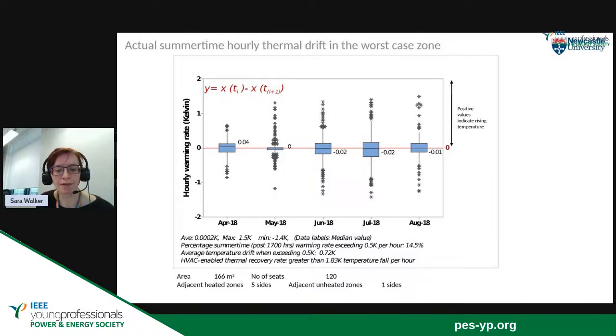Cooling was happening relatively slowly, but for some periods of the year, during the cooling period, warming up was happening faster than comfortable for over 14% of the cooling period that we looked at. So we can offer demand response in summer, but potentially for some spaces, or when external temperatures are particularly high, we might not be able to offer demand response because of this slightly faster warming up of the building.